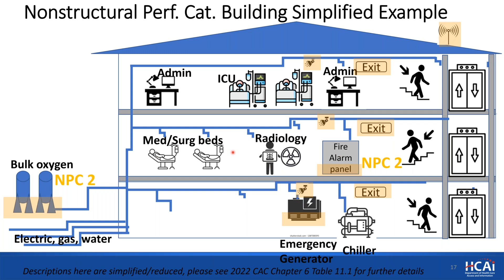The NPC2 brings in and anchors bulk oxygen, emergency generator anchoring, some fire alarm panels, exit signs, some lights, and some communication systems. So that would get NPC2. And if you want to go to NPC3, certain critical care areas get braced within the boundary. For example, if we take this ICU room, there will be some braces on these pipes, but not braces all the way around it. So NPC3 basically makes sure that things don't fall on the patients, but that doesn't mean that the room will be functional. NPC4D level 1 is basically NPC3 with our operational plan stated. NPC4 is basically looking at the entire building and bracing what's needed to make sure that it remains functional.